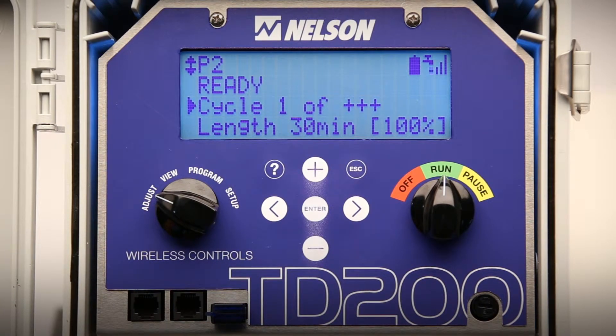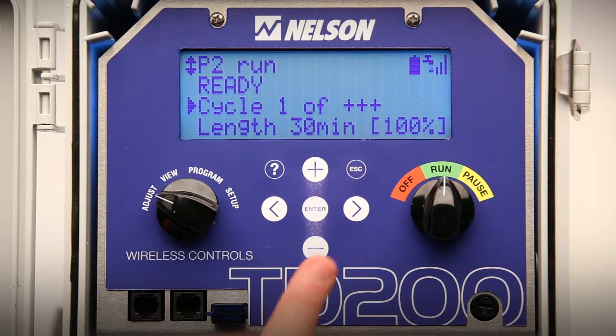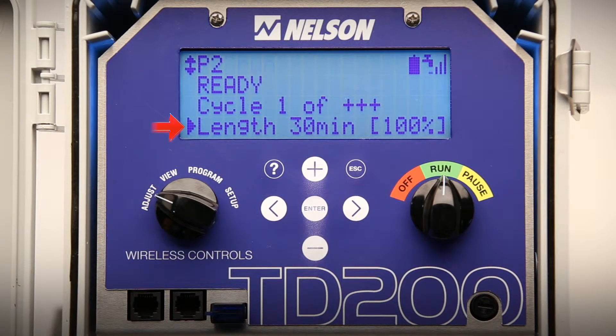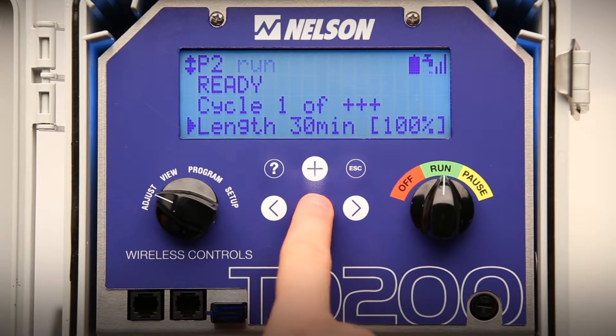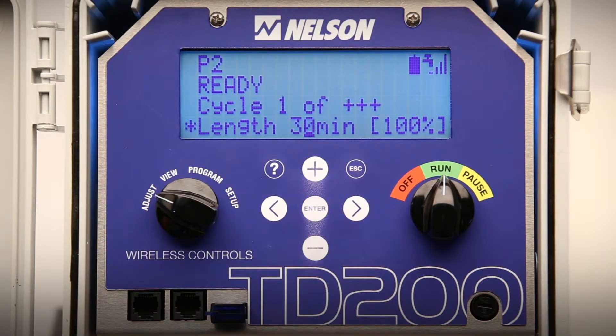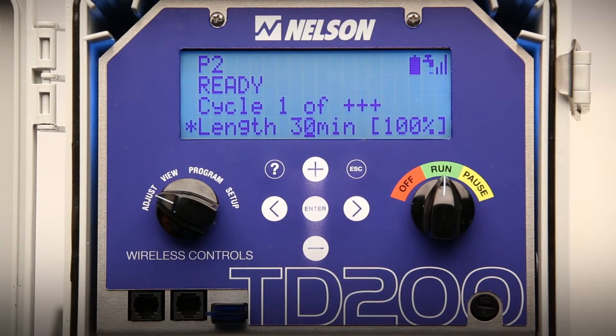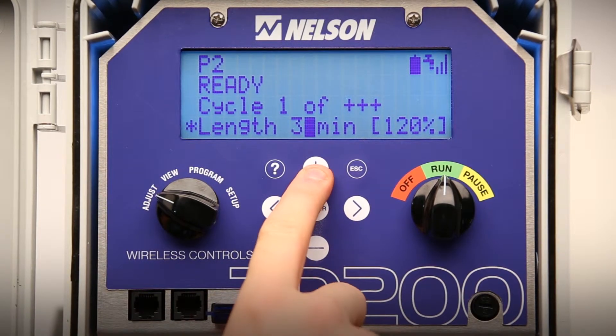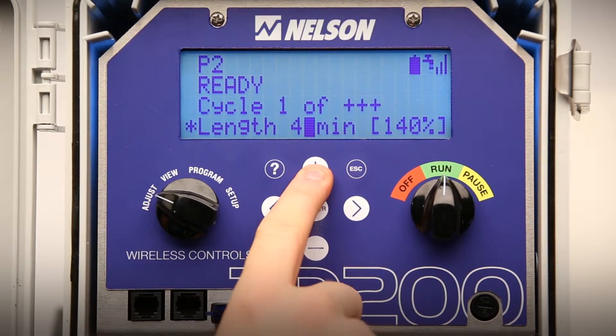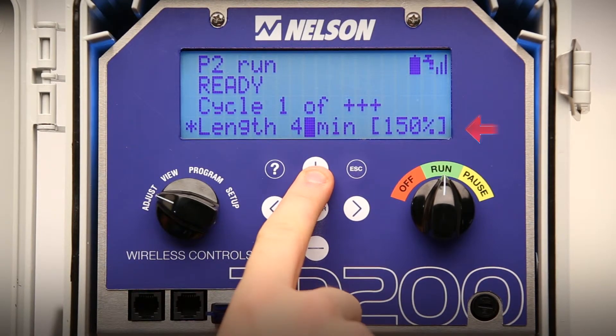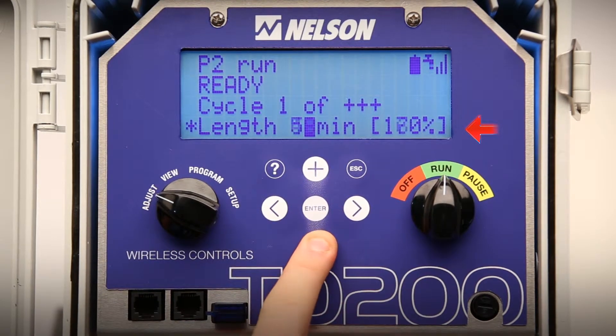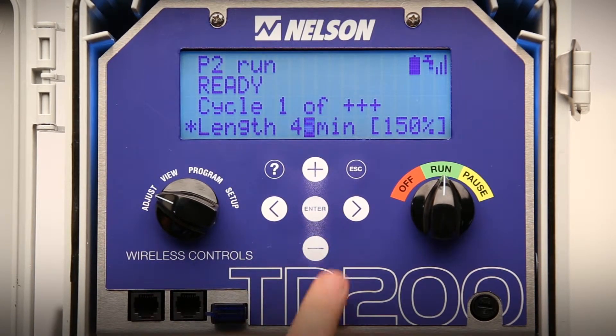Pressing the minus key will move the line marker down to length. Length is the amount of time to complete one cycle. Press enter and a flashing cursor allows you to press plus or minus to change the cycle time. Note that as you press plus or minus, the percent change will indicate what percent the cycle time has been changed. Press enter and the change will be saved.